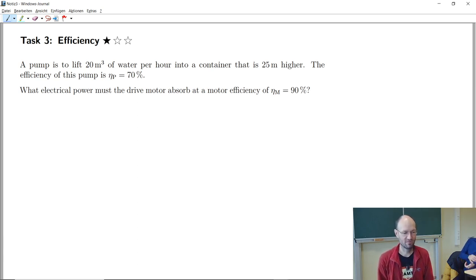So this third task is about a pump that lifts up a certain amount of water into a container that is 25 meters higher and the efficiency of the pump is given by 70 percent and we should calculate the electrical power for some drive motor. The efficiency of the motor is given by 90 percent. So you have a garden somewhere on a hill, you have a swimming pool with 20 cubic meters and your guests will arrive in one hour. So the question is what pump do you need to fill the swimming pool right on time before your guests arrive?